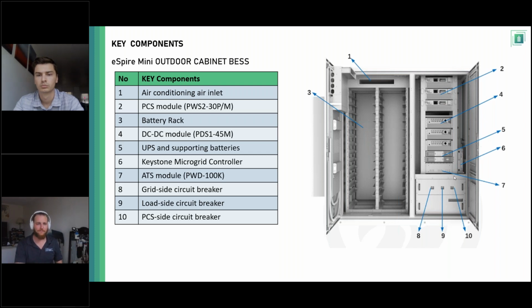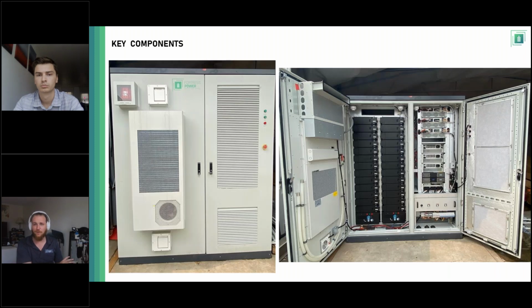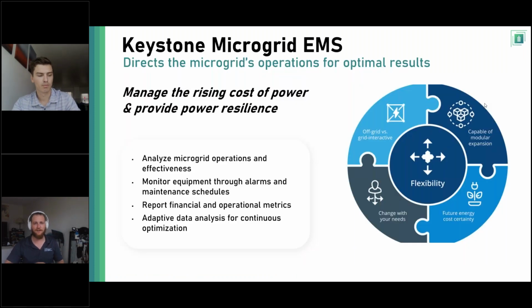So that's a rendering. I want to show you what that actually looks like in our facility. This is a fully loaded cabinet: 266 kilowatt hours of energy storage, 90 kW of inverter power at 480 volt, and 3 DC to DC modules to give you 130 kW of DC coupled solar. And again, like I said, same exact microgrid controllers, same exact EMS controls.